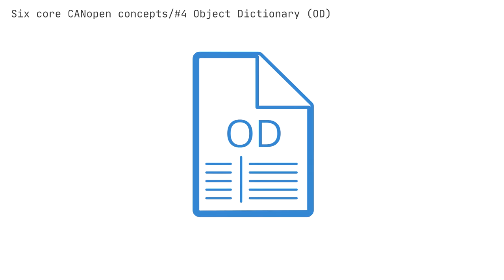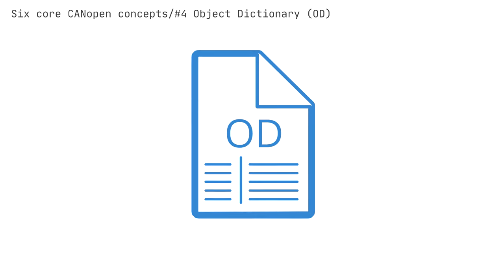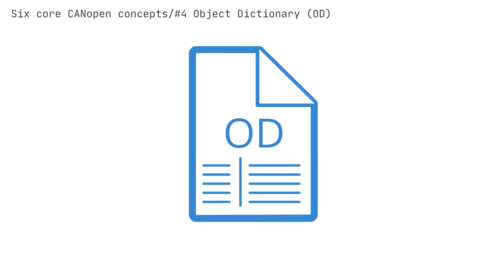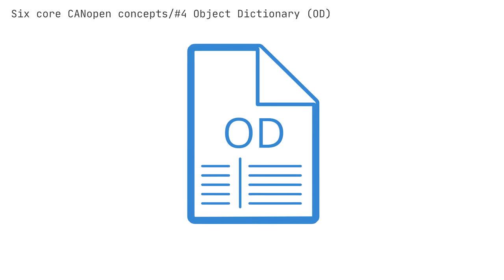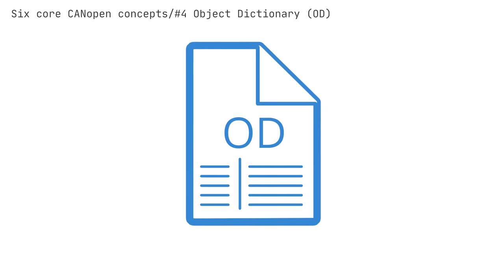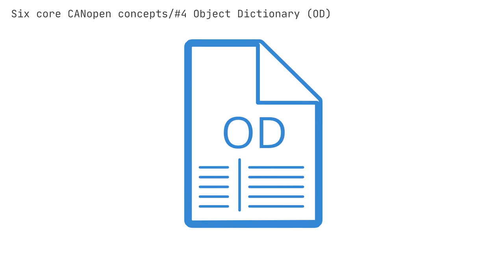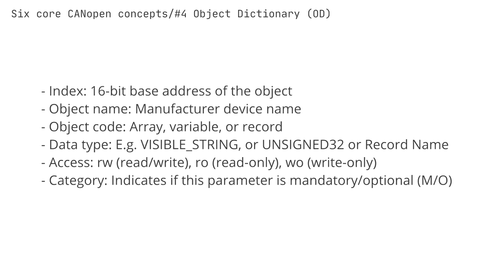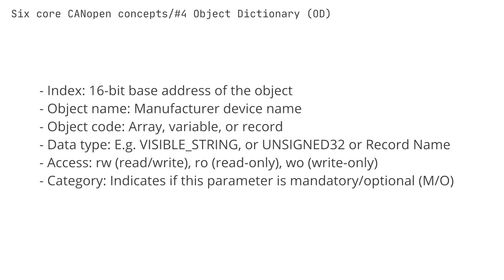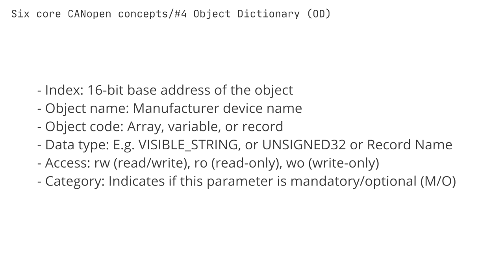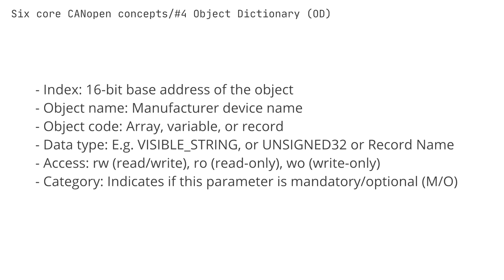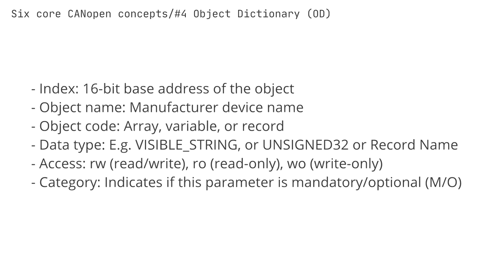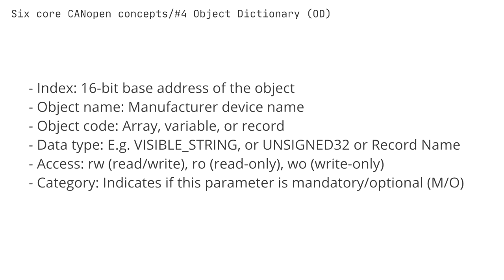All CANopen nodes must have an object dictionary (OD). The object dictionary is a standardized structure containing all parameters describing the behavior of a CANopen node. OD entries are looked up via a 16-bit index and an 8-bit subindex. For example, index 1008 subindex 0 of a CANopen-compliant node OD contains the manufacturer device name. An entry in the object dictionary is defined by attributes: index (16-bit base address), object name, object code (array, variable, or record), data type (e.g. visible_string, unsigned32, or record name), access (RW, RO, or WO), and category (mandatory or optional).